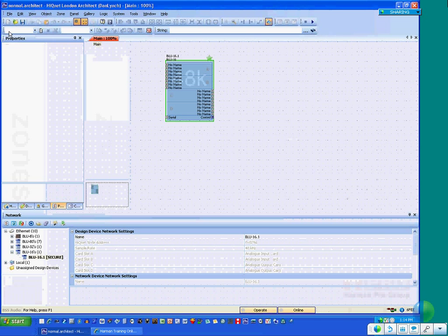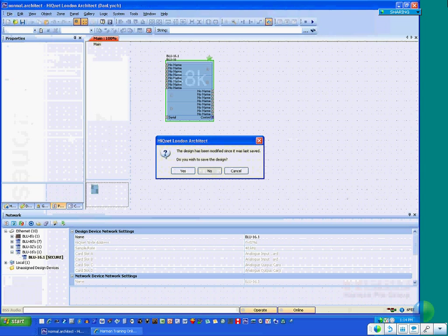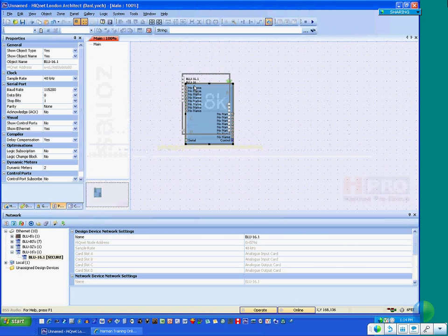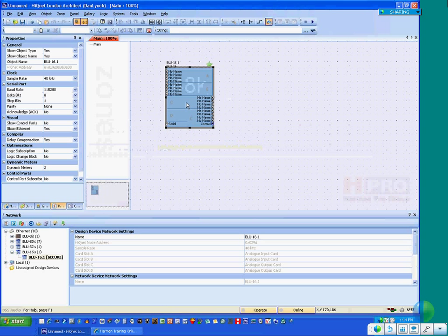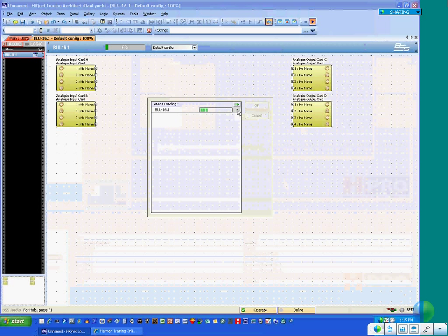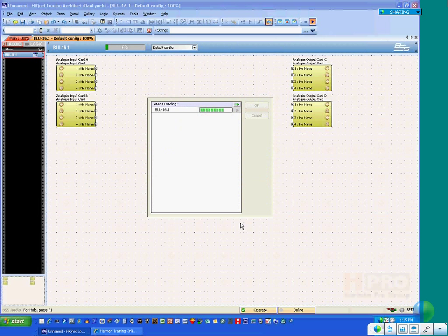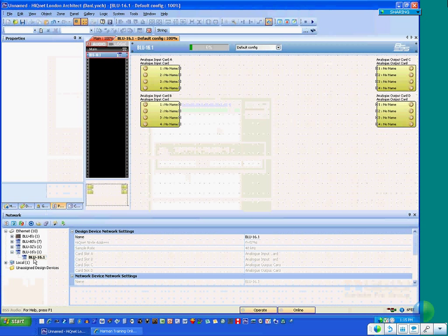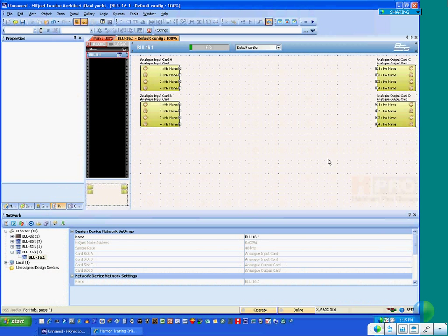So here's my device. It's been secured again. Now, instead of turning off box security in that design file, I can create a new design file with nothing in it. Just put the device in there, no programming. Load that design file. It's going to ask me for the password. And load it up. Now that device has effectively no programming, and the box security password has been removed. Look right there, it's not secure anymore. That's how you keep your system truly secure.